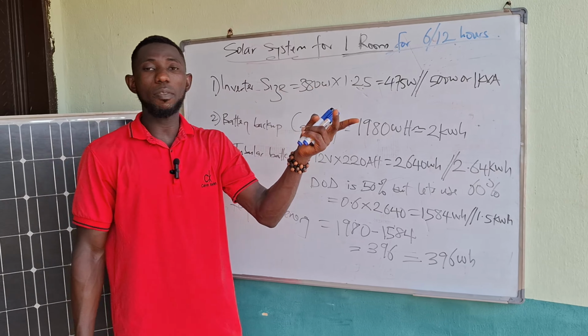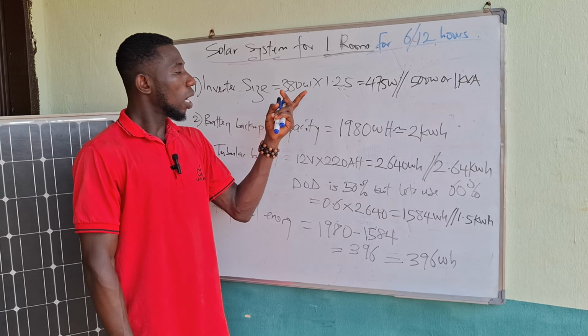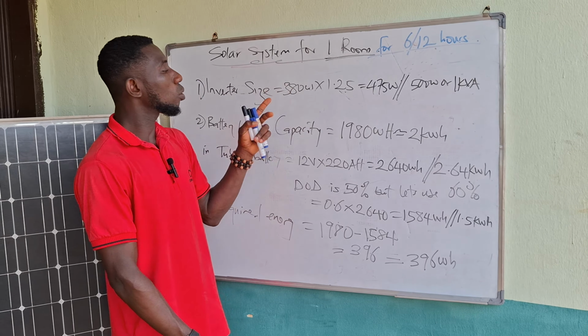In this place, from our previous calculation, our load total is 380 watts. We use 1.25 as our safety margin, because when you want to use an inverter to power anything or switch on the solar system, you give tolerance, since there are things inside the system that might overpower it, or you might bring extra things, or we simply don't have that exact kind of inverter in the market. Also, you cannot use an inverter capacity equal to the load itself, 380 watts to power a 380 watt load. It doesn't work like that; the inverter will trip up because it cannot carry that amount of load.